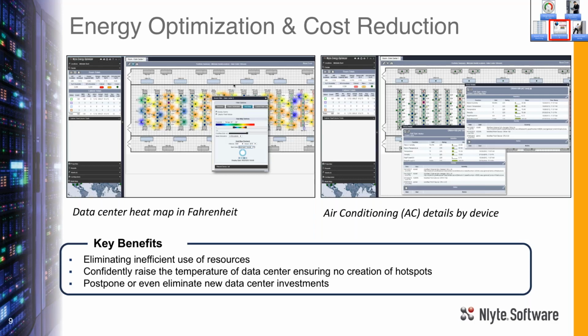So we like to use a heat map a lot, and see how that correlates to our power consumption. At the same time, we can distribute the equipment a little more evenly to make sure we're using our raised floor cooling to 100%, and not losing energy to an empty cabinet or an empty row.